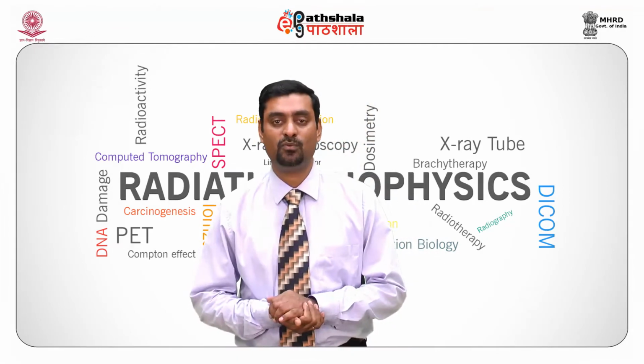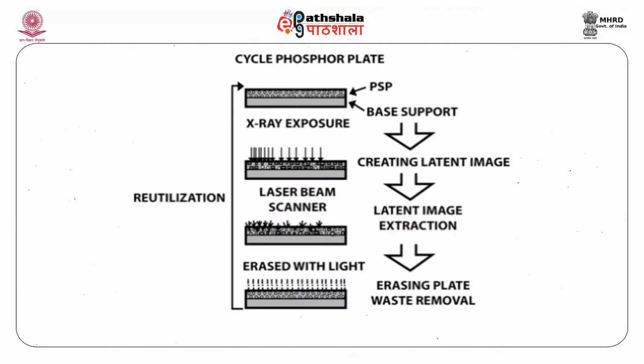Let's summarize what is present in this computed radiography system. The IP plate, which has the barium fluorobromide, creates a latent image when X-rays are exposed to it. When a laser beam is scanned on that, the latent image gives the image formation. And finally, a little bit of latent image is still present, which has to be erased by intense light. However, this entire IP plate can be reused after erasing, so that the residual latent image is removed from the plate.